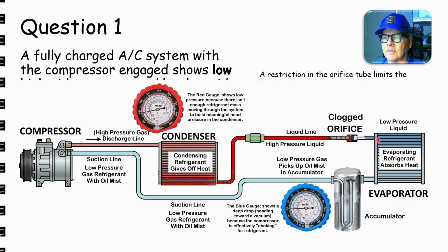In normal circumstances, this low pressure liquid goes into the evaporator and turns into a gas. It boils at like 21 below zero, depending, and so then it comes out of here as a low pressure gas. Any condensation of the refrigerant, there's liquid refrigerant and there's oil mixed with it in here. Some of that's picked up. There's a screen here, a little tiny hole in this tube. It picks up oil in there and draws it out.